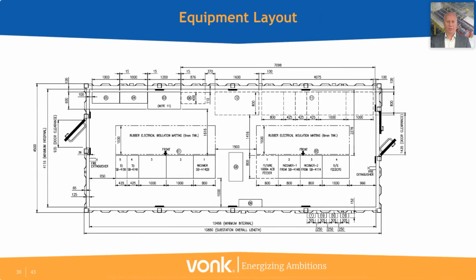Pictures say more than words, but during the design phase you need to know where equipment will be placed within the building, taking into account its size and the escape routes between equipment, as well as door placement. You can see a double-leaf door on the right here and a single one on the left.